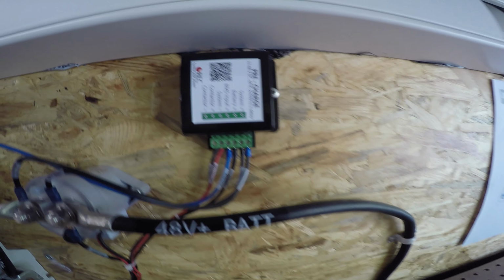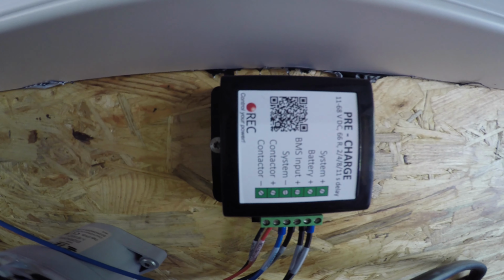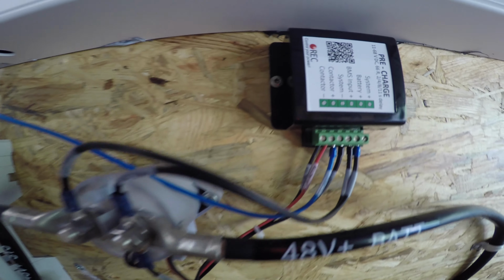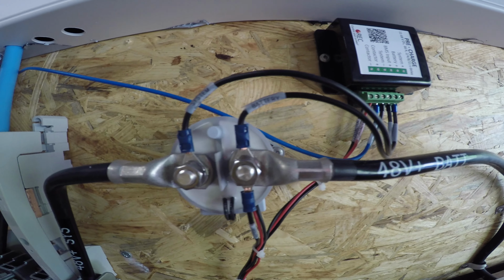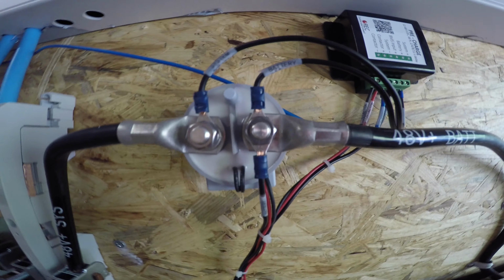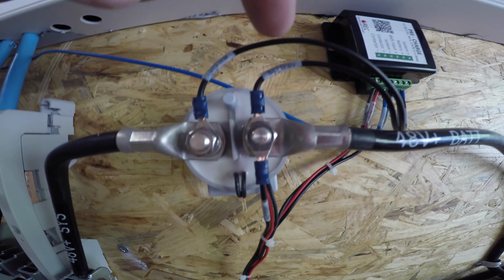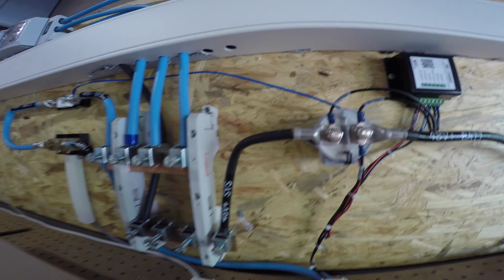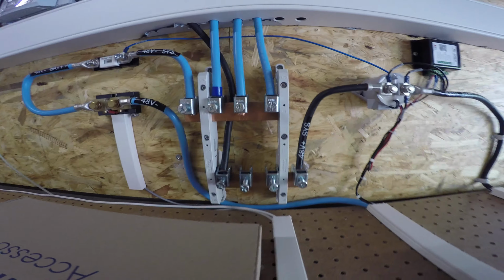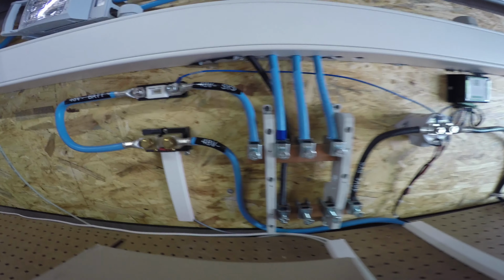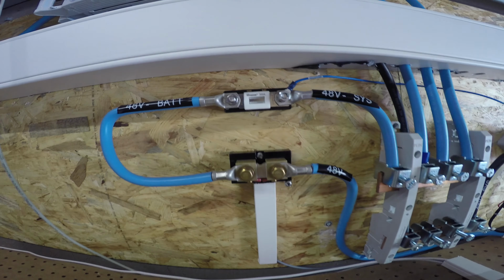There's a pre-charge controller connected to the relay, which allows a small current to pre-charge the Sunny Island instead of a cold connect to the battery, which creates a lot of inrush current you don't want - it damages the electronics and limits the lifespan.